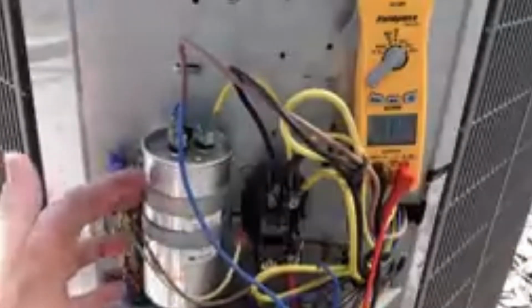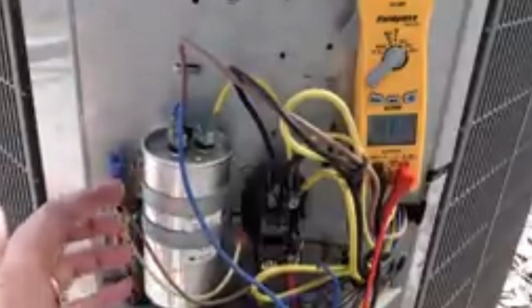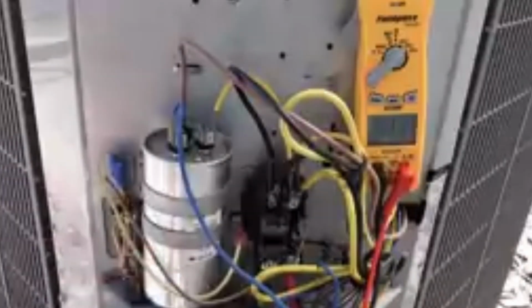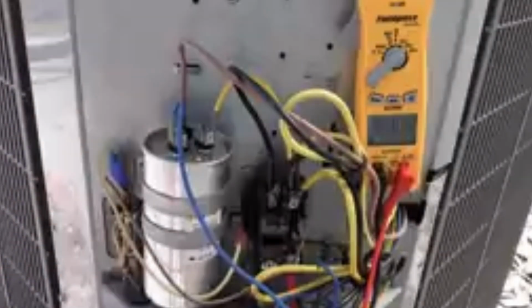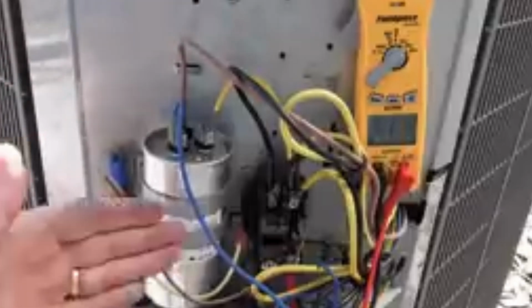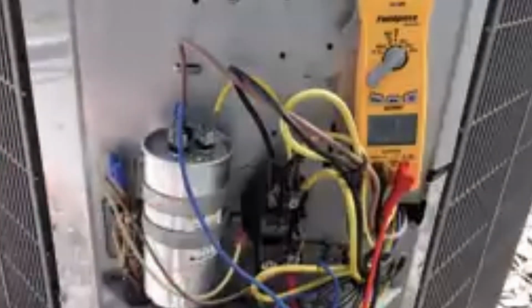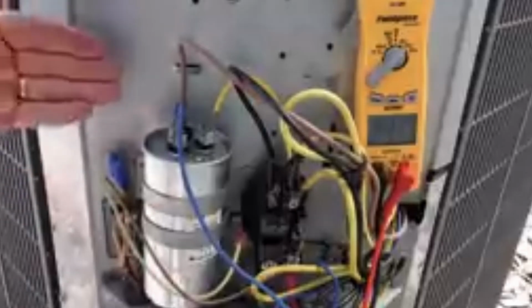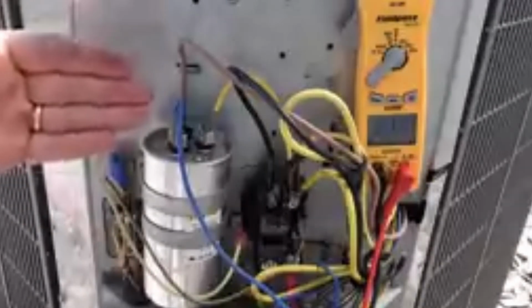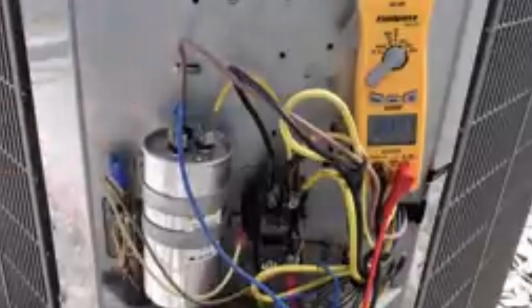In order to measure the microfarad reading of our run capacitor, we could either do it while the system is running by using some basic math that we show how to use inside the HVAC School app, or we could disconnect the wire, make sure that it had no stored charge by jumping across it with a resistor, and then measure the microfarads. Every capacitor is going to have a microfarad reading on the data tag, and the easiest way to do it is simply to disconnect the terminals and measure from C to Herm and then C to fan on the dual run capacitor for your measurement.